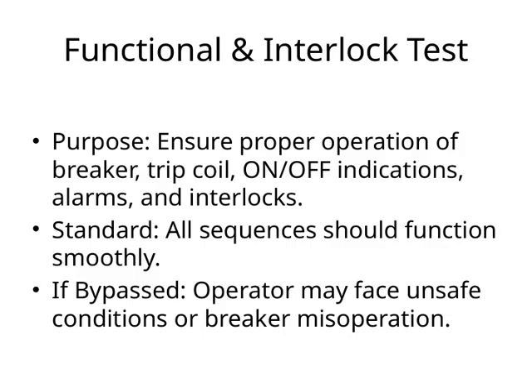Now, let's talk about the functional and interlock test. The main purpose here is to make sure that everything operates correctly, so that the breaker, trip coil, on/off indicators, alarms, and interlocks all work as they should. It's essential that all these components function together seamlessly to maintain system safety and reliability. We expect all sequences to run smoothly, meaning no unexpected delays or failures during operation.